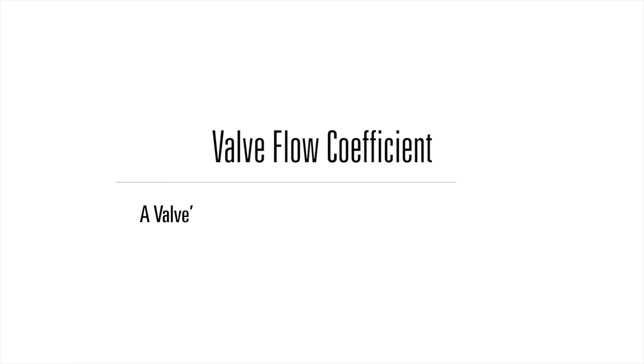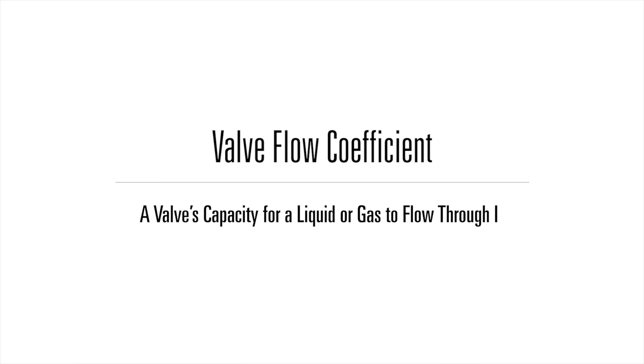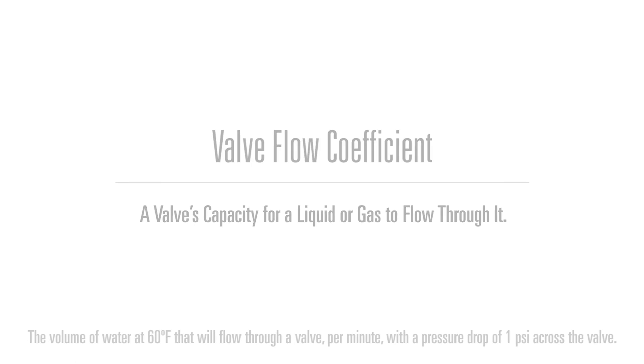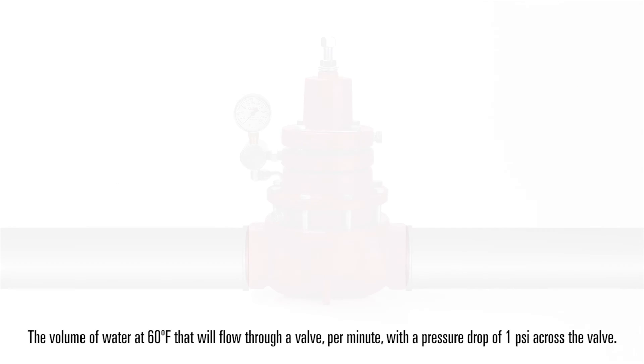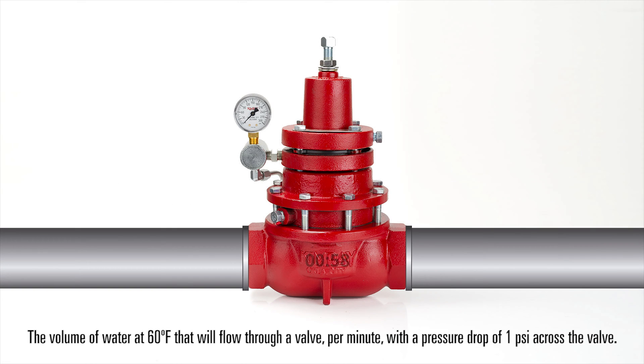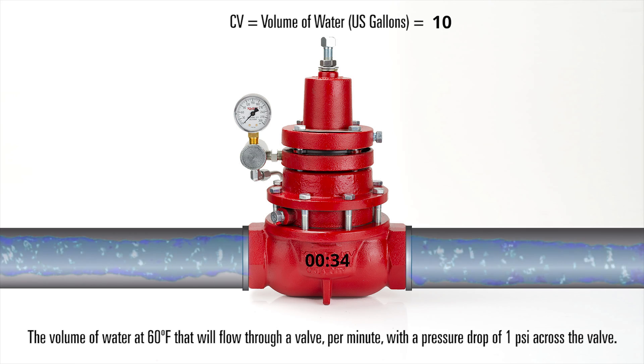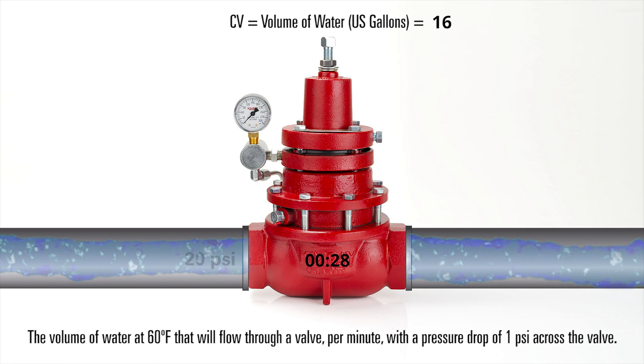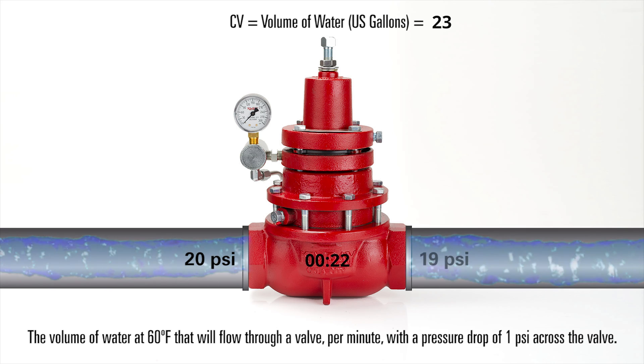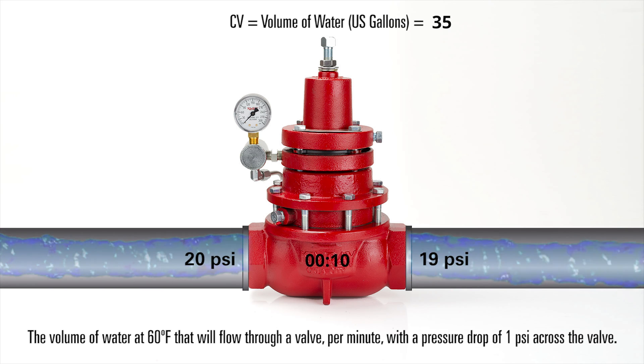Valve flow coefficient is a valve's capacity for a liquid or gas to flow through it. It's technically defined as the volume of water at 60 degrees Fahrenheit that will flow through a valve per minute with a pressure drop of 1 psi across the valve.